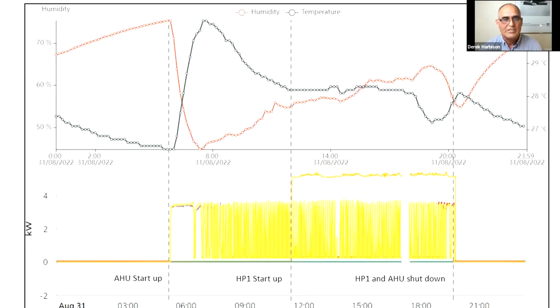It's got a pool cover on, but the system goes off, the temperature's dropping away. As soon as the air handling unit comes on, it basically inverts that climb, so our humidity drops, the temperature rises, and it overcompensates. The rest of the time, between about 6:30 or 7 o'clock, we've now got this downward slide until the system sort of balances itself.